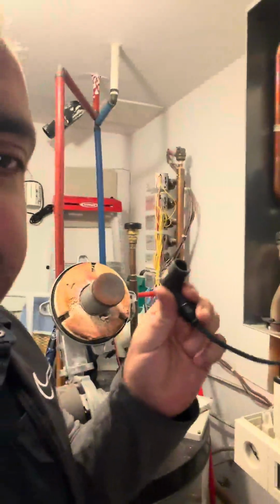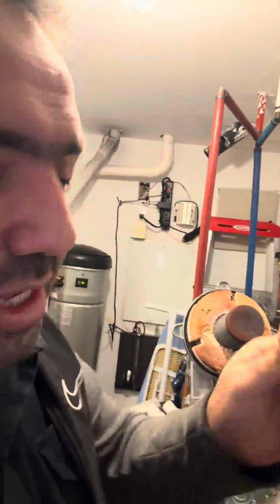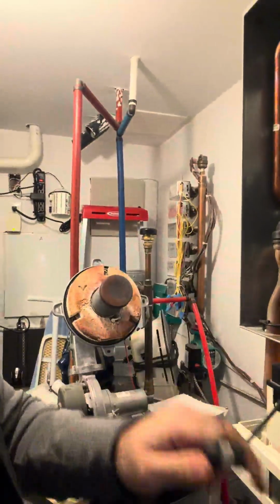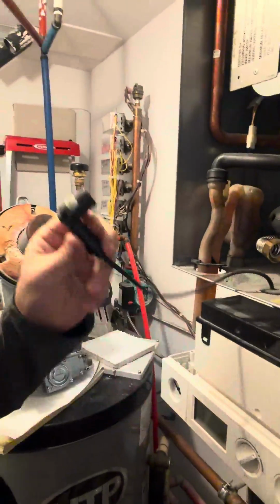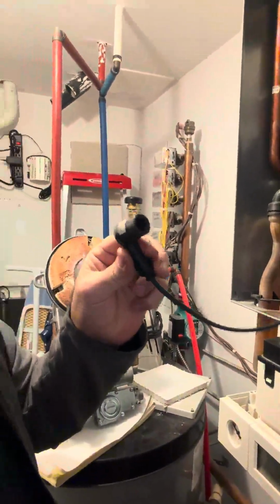If the igniter replacement and cleaning doesn't work, then sometimes this wire, which connects to the igniter and goes to the control board here, is the problem, which is really rare, but it happens. So I'm just in the middle of doing the job. I have to clean it, replace the igniter, and see how it goes, and then I'll keep recording and show you the result.